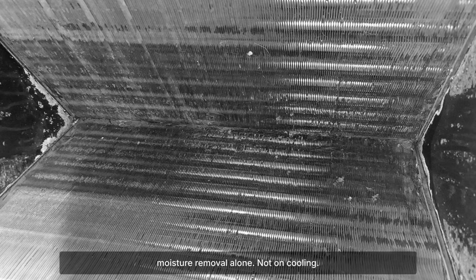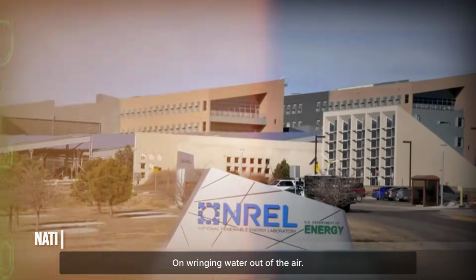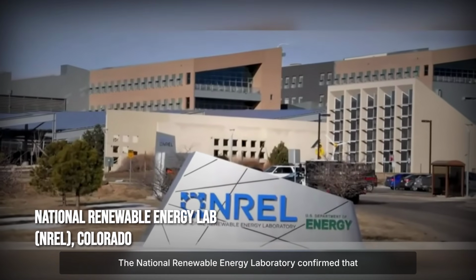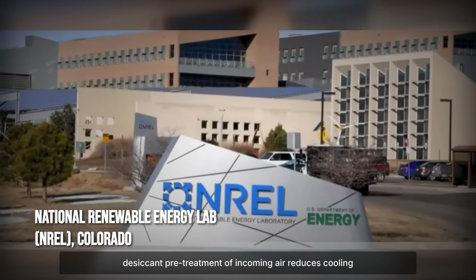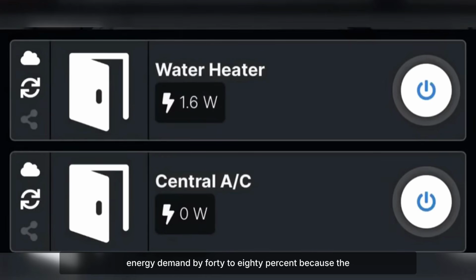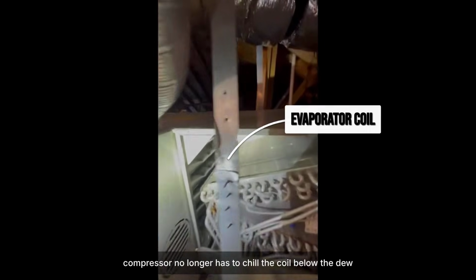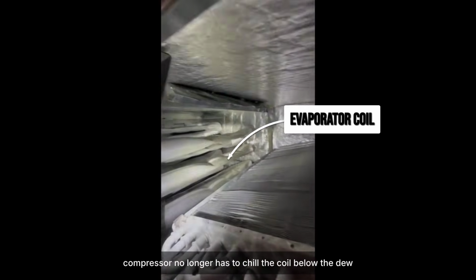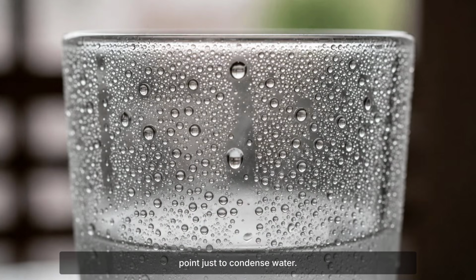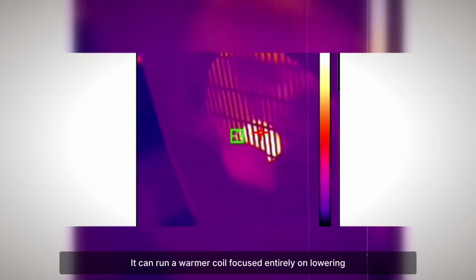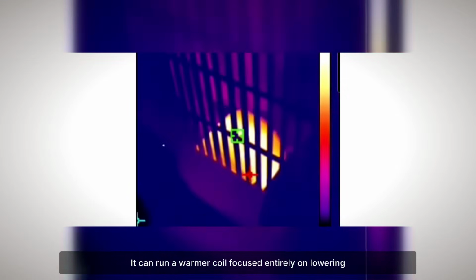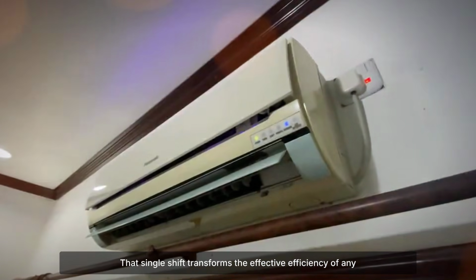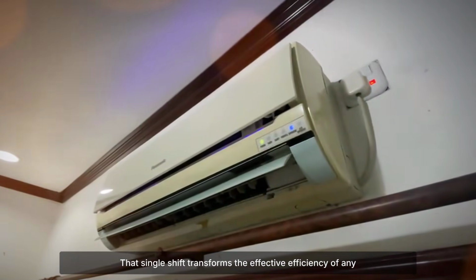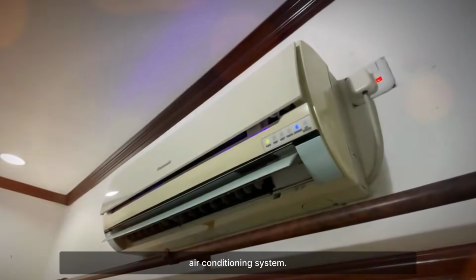Not on cooling, on wringing water out of the air. The National Renewable Energy Laboratory confirmed that desiccant pre-treatment of incoming air reduces cooling energy demand by 40 to 80%, because the compressor no longer has to chill the coil below the dew point just to condense water. It can run a warmer coil focused entirely on lowering temperature. That single shift transforms the effective efficiency of any air conditioning system.